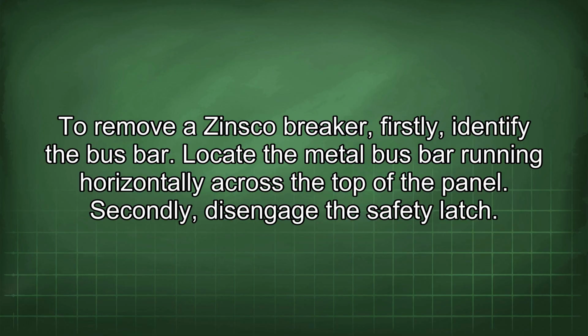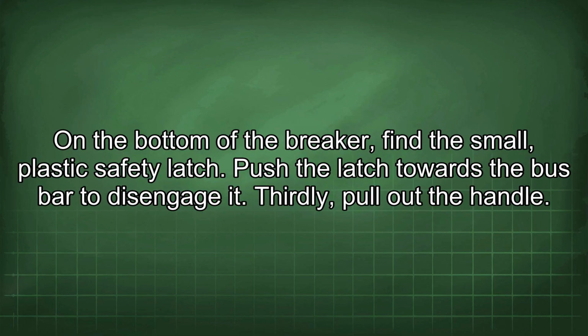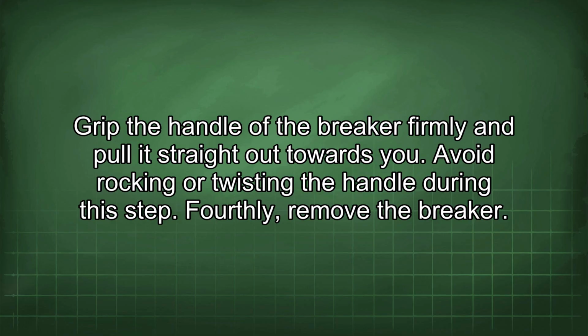Secondly, disengage the safety latch. On the bottom of the breaker, find the small plastic safety latch. Push the latch towards the bus bar to disengage it. Thirdly, pull out the handle. Grip the handle of the breaker firmly and pull it straight out towards you. Avoid rocking or twisting the handle during this step.